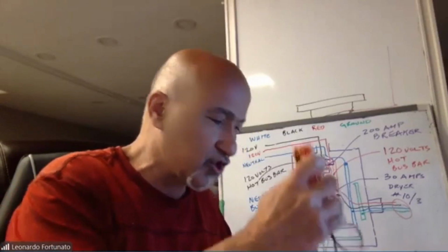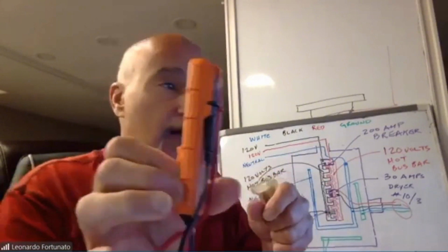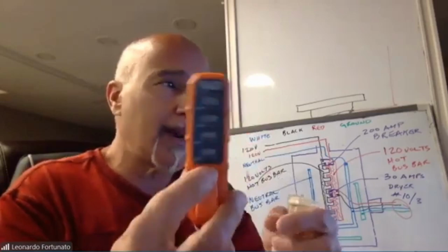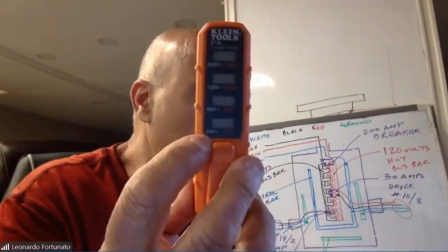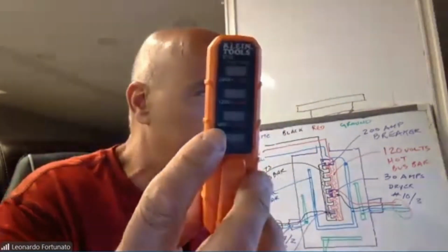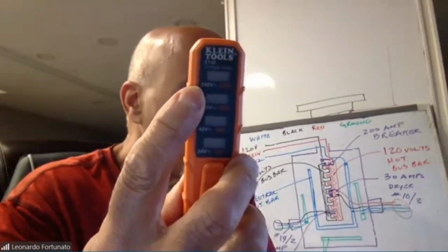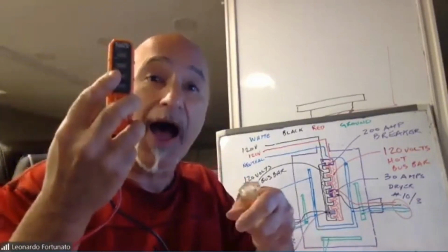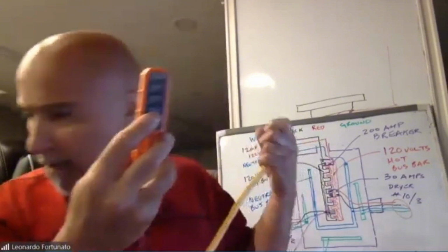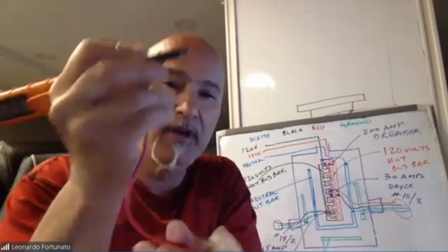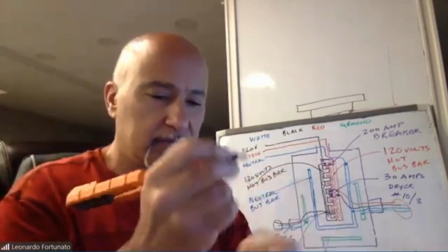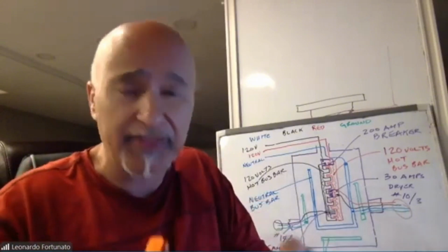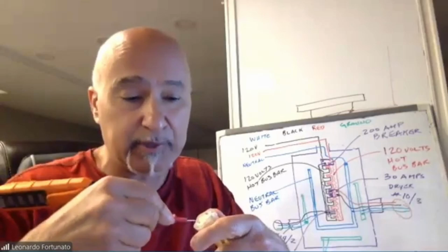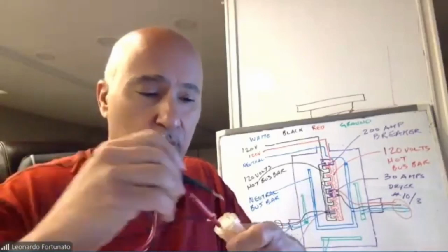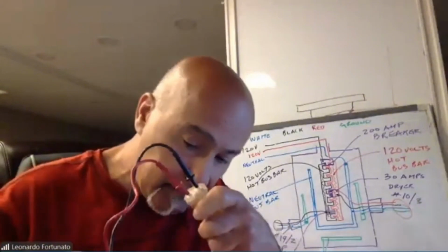Let's take a look at one which is a little bit better than that one. Same concept, ladies and gentlemen. This one will allow me to test anywhere from 24 volts low voltage, 48, 120, to 240. Of course, we have other testers that can test for higher voltage, I'll show you one of those later. Anyhow, that being said, same idea: I can either put these little tips on my contacts or take these little sleeves off. You'll see we're working with 120 volts here, so when I plug this in, it's going to light up to 120 volts. You can see over here, there you go.